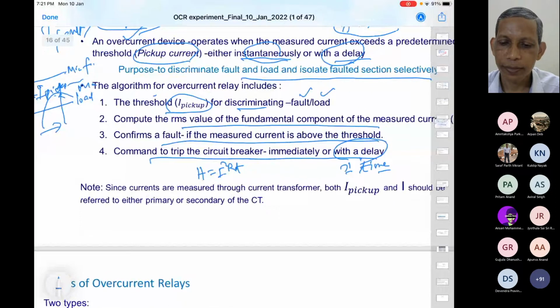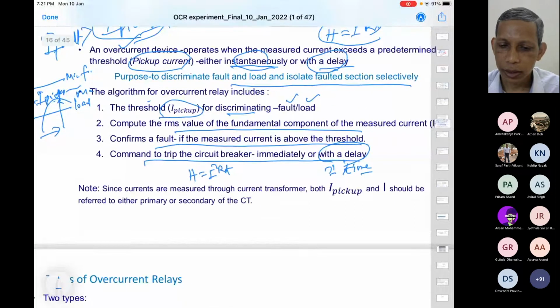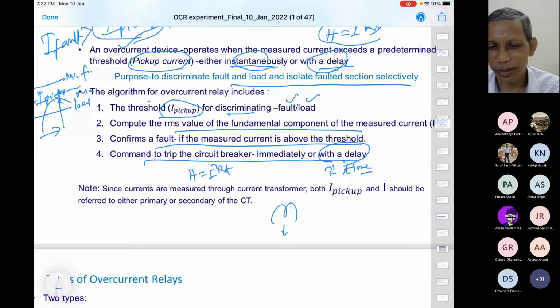In numerical relay, in the analog form of relay, there is no brain calculation. So whatever the CT secondary, you understand CT secondary? This is the CT secondary side. The CT secondary current actuates the relay. So the relay sees only that current.